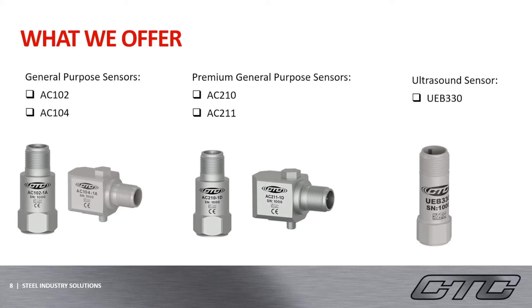These sensors are efficient in every environment in the industrial world and come in both cost-effective and premium options. They come in both top exit and side exits, made with 316L stainless steel, and are all hermetically sealed, meaning these sensors are very ideal for this type of environment, as the seal blocks any materials and liquids from entering the sensors. These 100 mV/g 2-pin dynamic sensors are perfect for most vibration readings within a facility. The main difference between the AC-102 and the AC-210 is the dynamic range: the AC-102 has a dynamic range of plus or minus 50 Gs, while the AC-210 has a dynamic range of plus or minus 80 Gs.